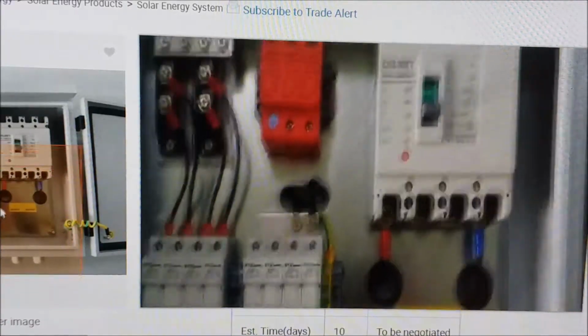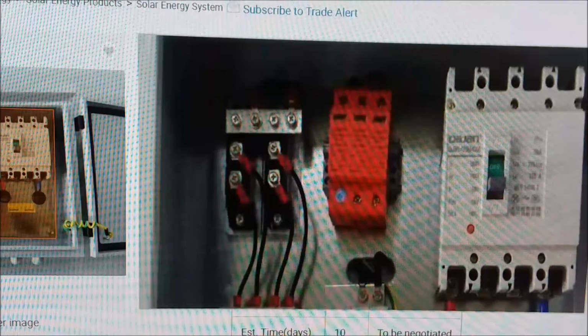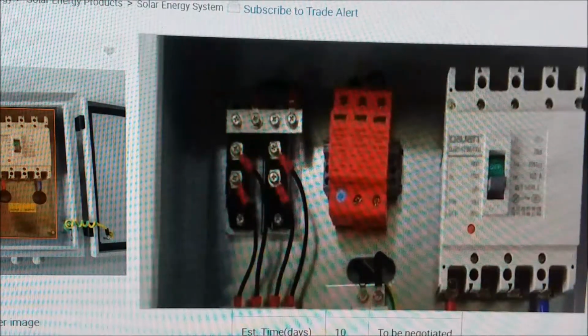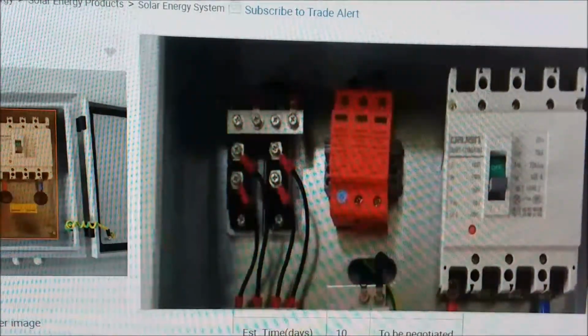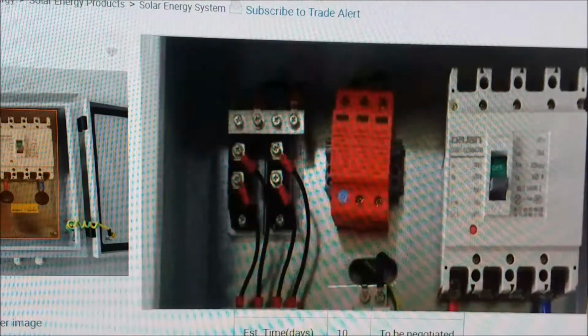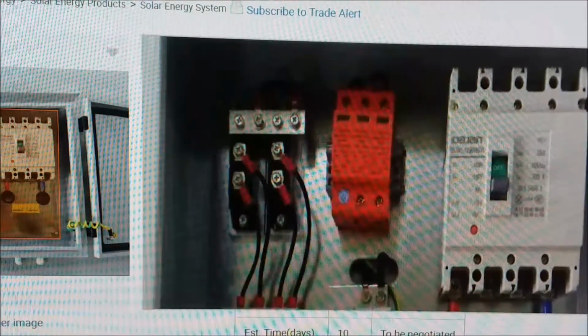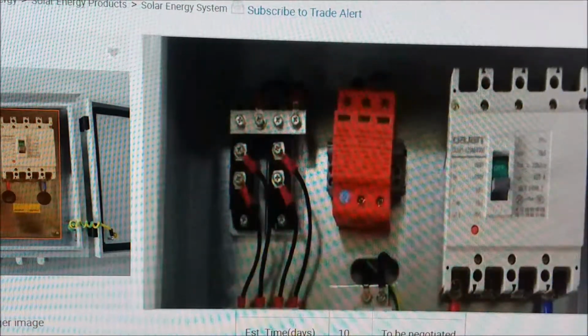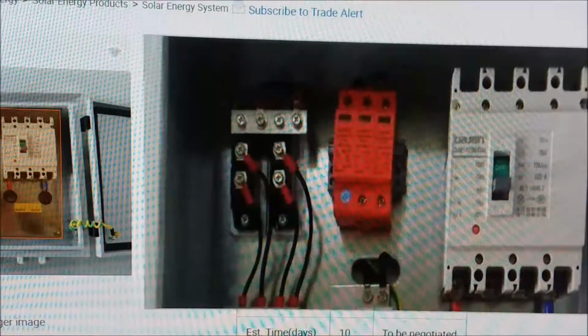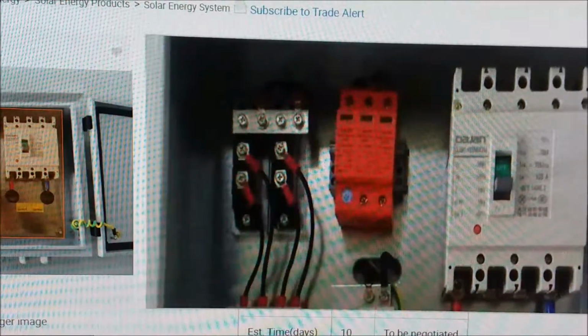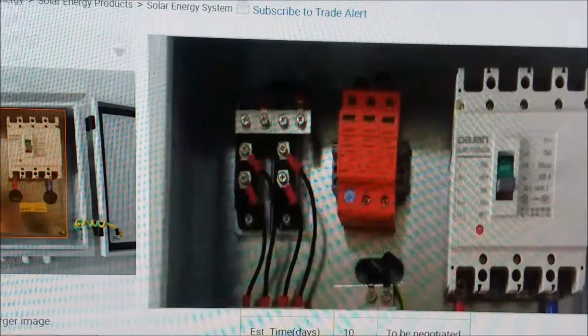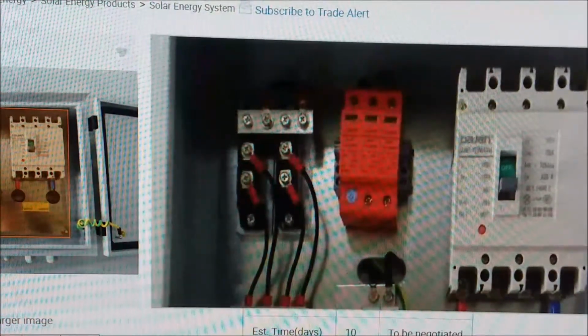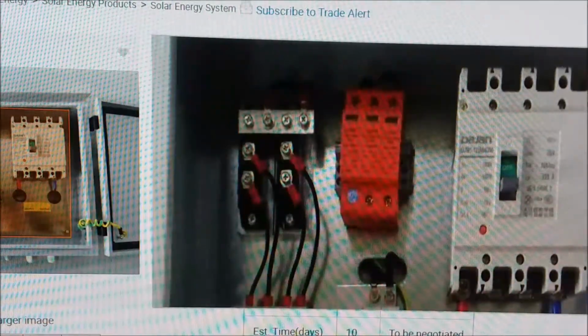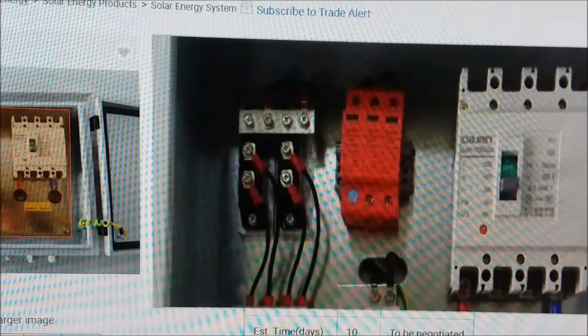Above that, in the corner, the black thing with what looks like 4 wires on it and a bus bar across the top - those are one-way diodes. They prevent you from hooking it up backwards and damaging your inverter. But once it's wired up, they still do something. They prevent drainage from your batteries through your inverters or wherever.